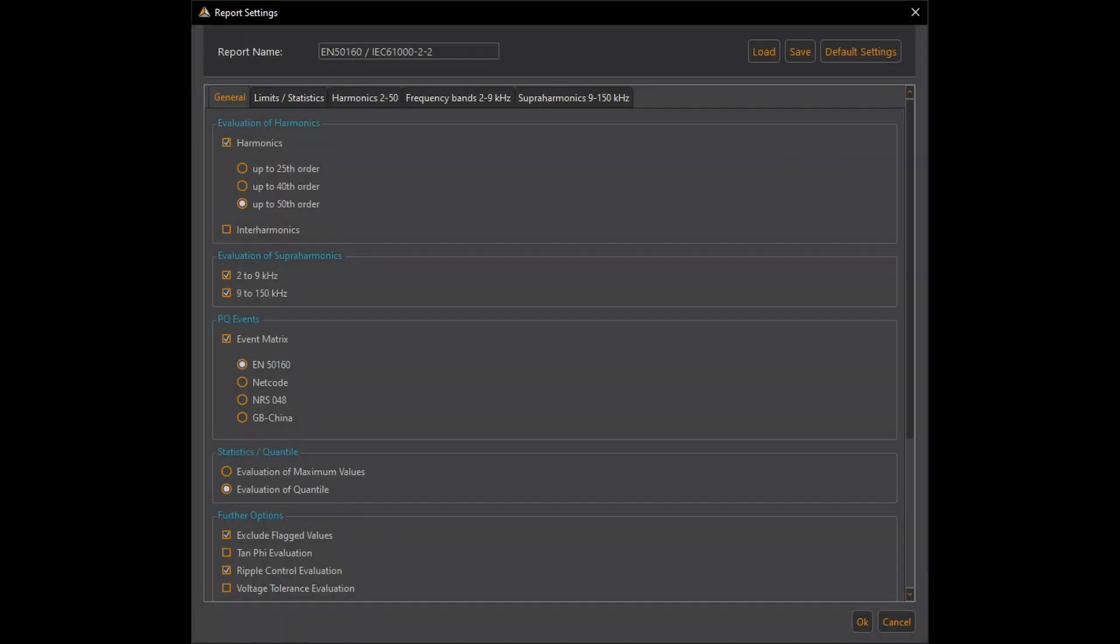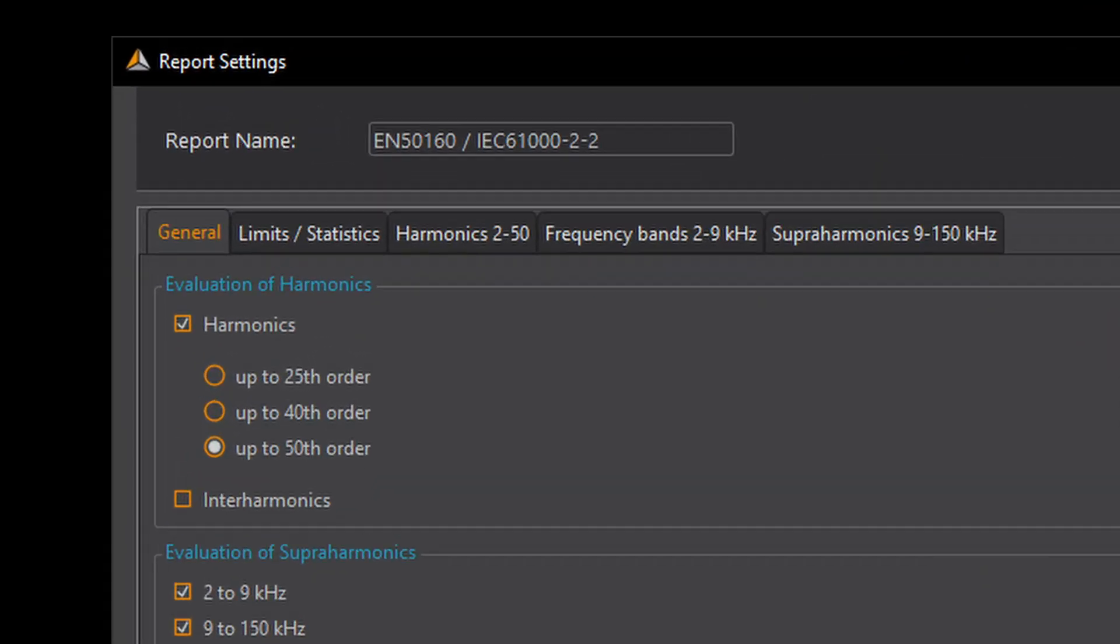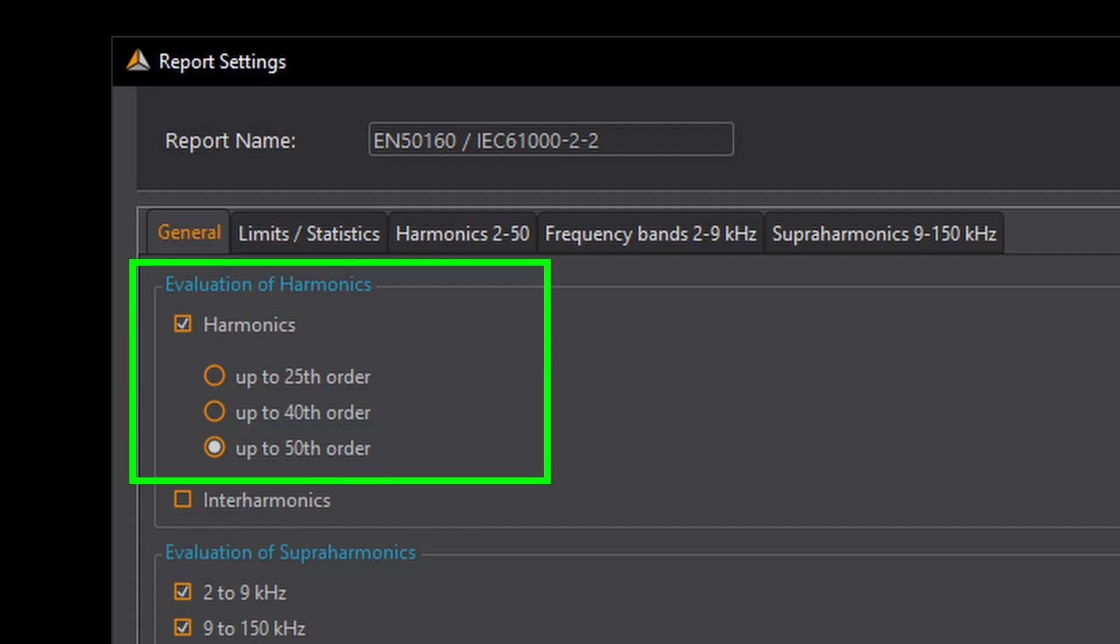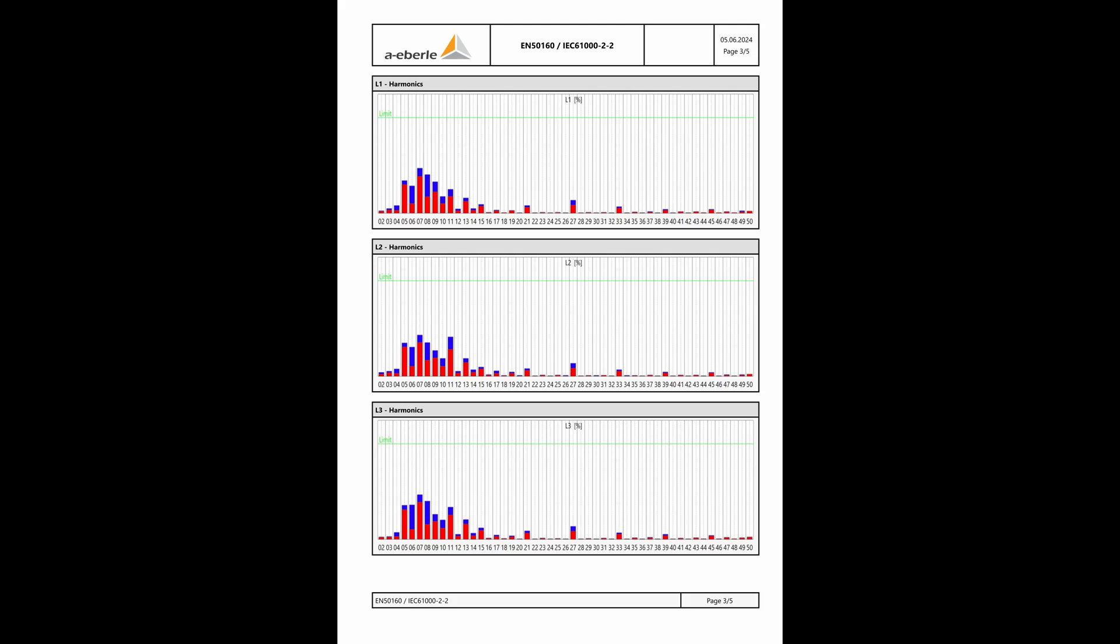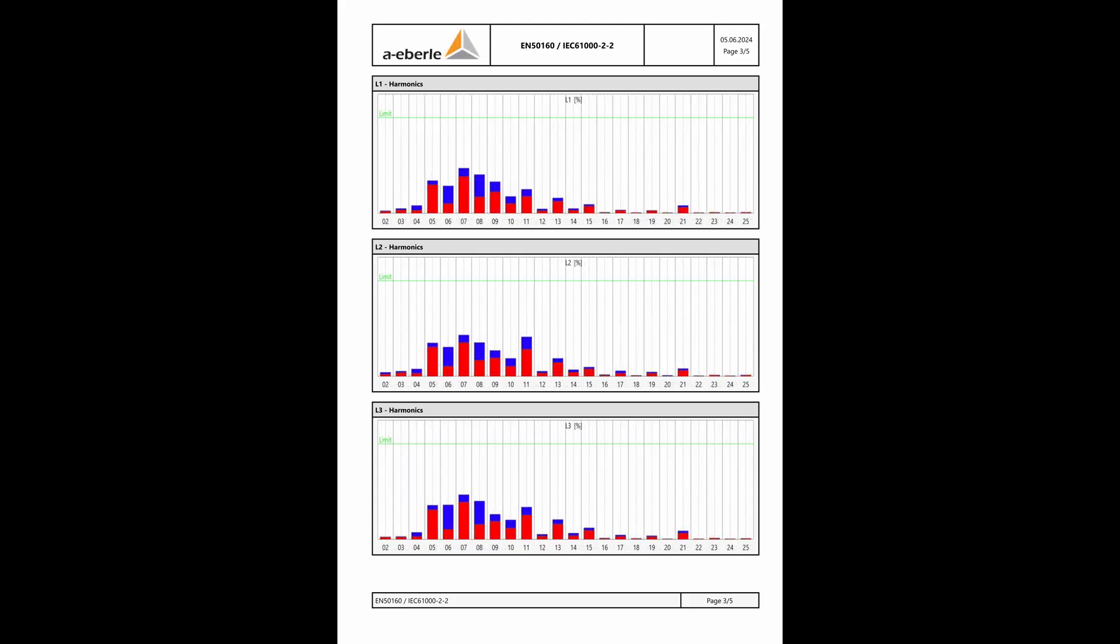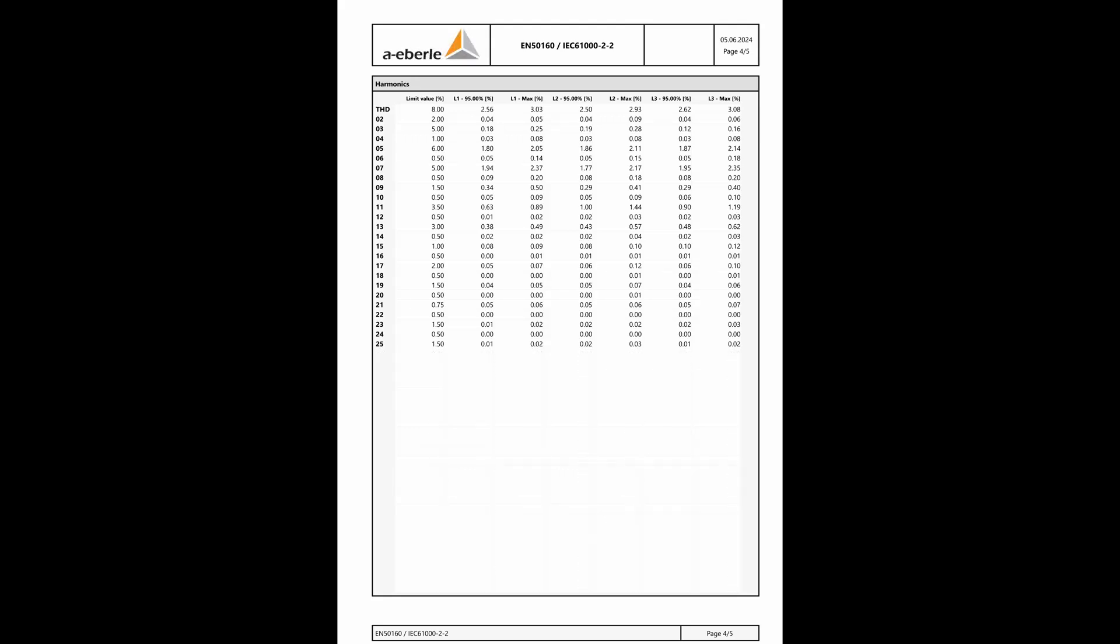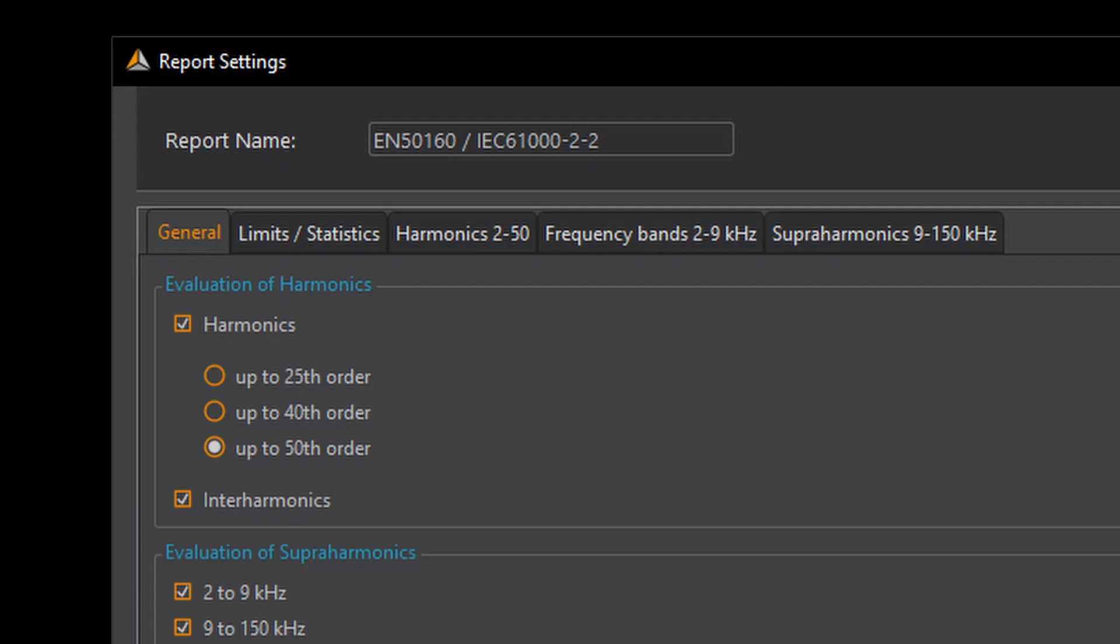In the general tab I can find further setting options which I will now explain. For the voltage harmonics I can choose between an evaluation up to the 25th harmonic, 40th or 50th harmonic. If I reduce the selection to 25 the report on page 3 only shows 25 columns per phase in the bar chart. And in the table on page 4 only the rows to the 25th harmonic.